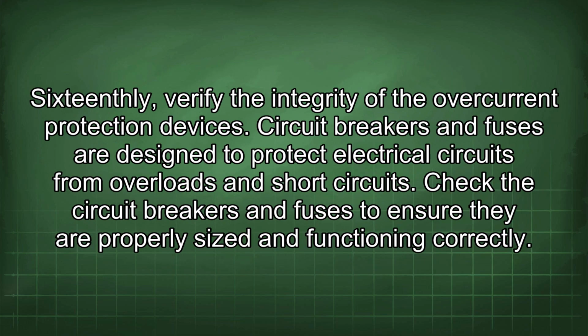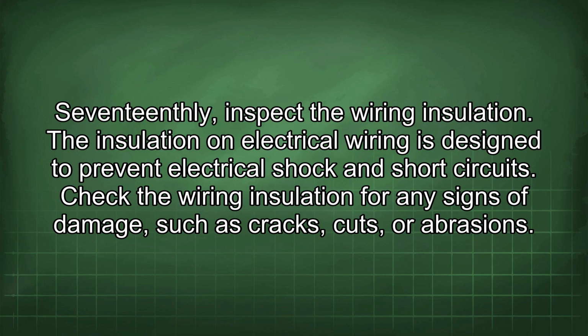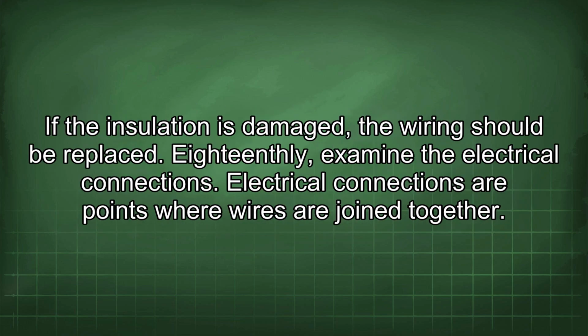16thly, verify the integrity of the overcurrent protection devices. Circuit breakers and fuses are designed to protect electrical circuits from overloads and short circuits. Check the circuit breakers and fuses to ensure they are properly sized and functioning correctly. 17thly, inspect the wiring insulation. The insulation on electrical wiring is designed to prevent electrical shock and short circuits. Check the wiring insulation for any signs of damage, such as cracks, cuts, or abrasions. If the insulation is damaged, the wiring should be replaced.